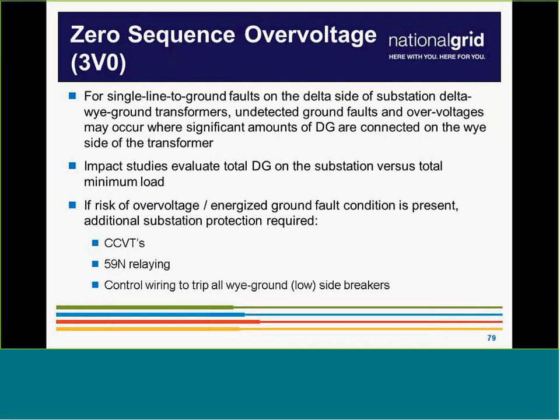So, 3V0. Who wants to know about 3V0? Can I get a show of hands on that? So, 3V0 is transmission ground fault protection. It's basically to make sure that your ungrounded or delta high side transformer... Now, keep in mind, ungrounded means either delta or ungrounded Y. Or in some cases, just where you don't have continuity where you can see the transmission system.